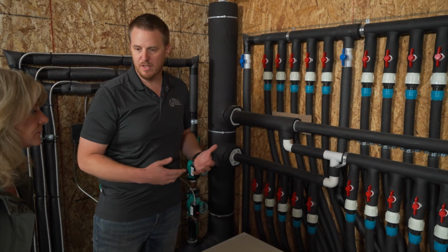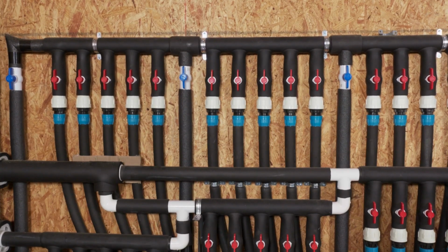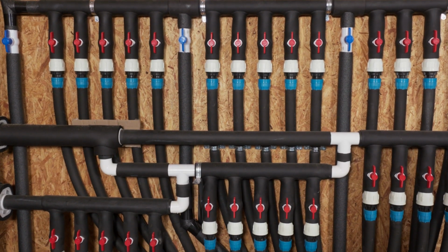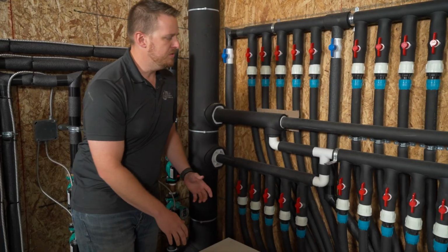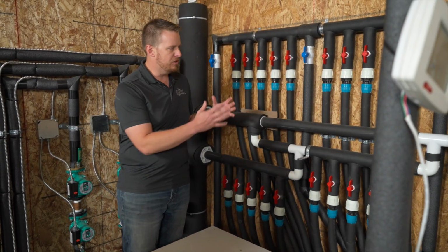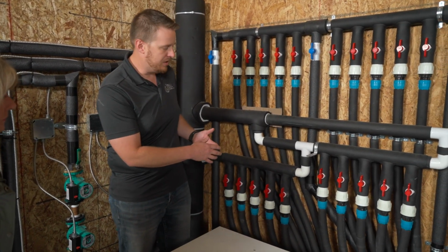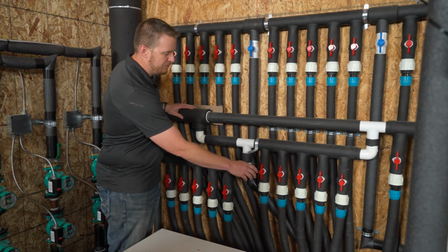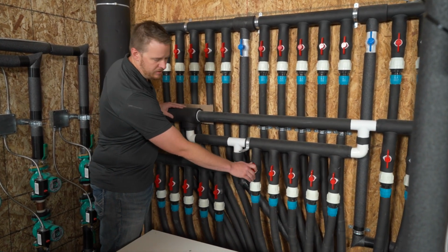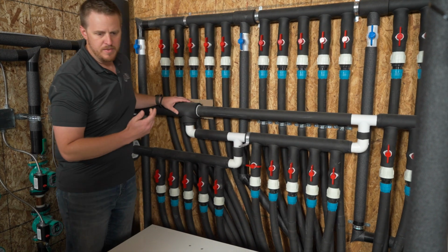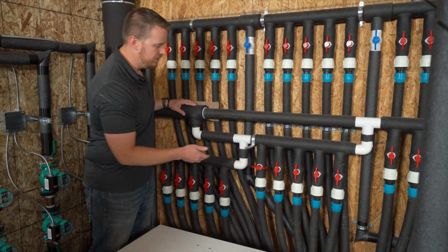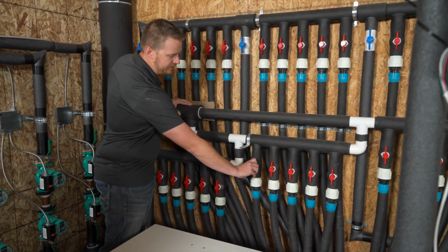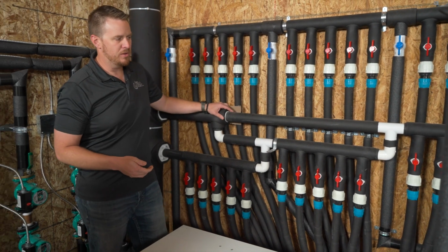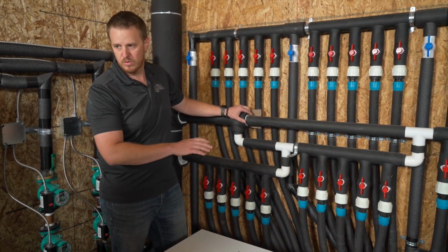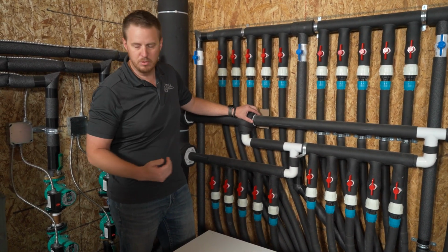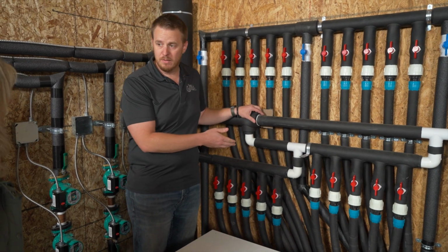This is what we were talking about, how we'd either do slinky or directional boring. But that pipe comes up on the wall and manifolds, and something unique that we do, we put all of our manifolding interior to the structure. We do that for a couple reasons. One, if one of them does get hit, you can isolate it and you're still up and running on everything else. We also put these ball valves in here from a test and balance standpoint, so if we need to adjust flow to balance things out so we get that proper heat exchange, we have that ability to do so.